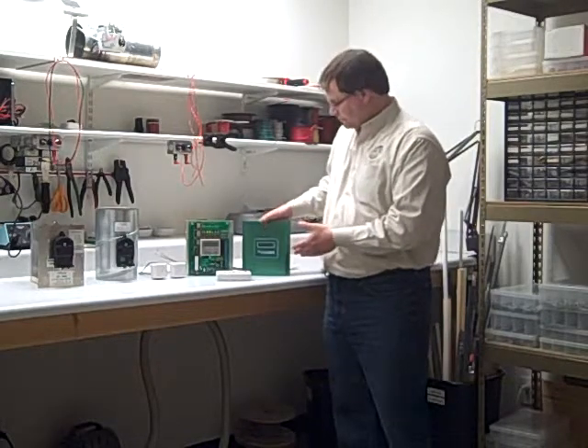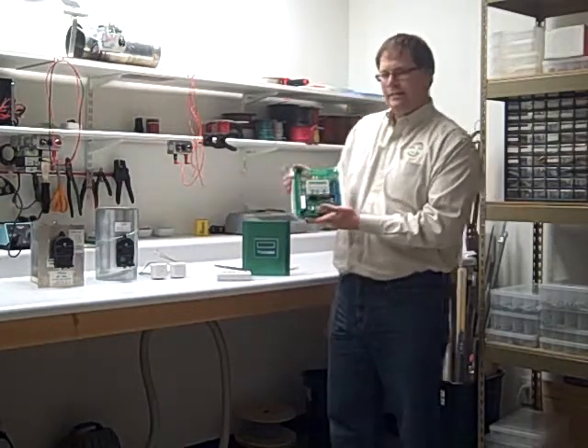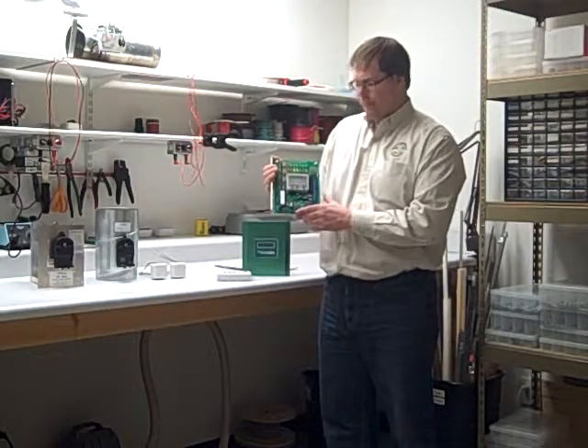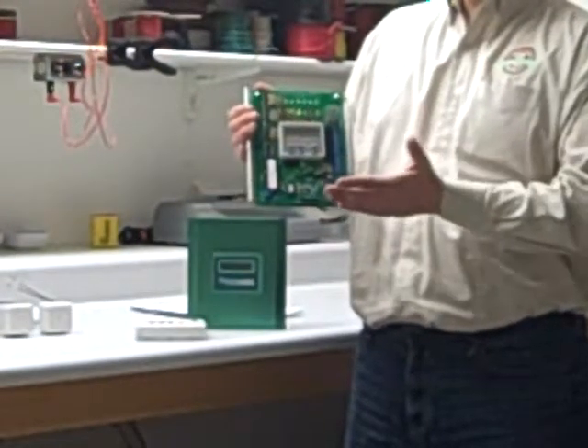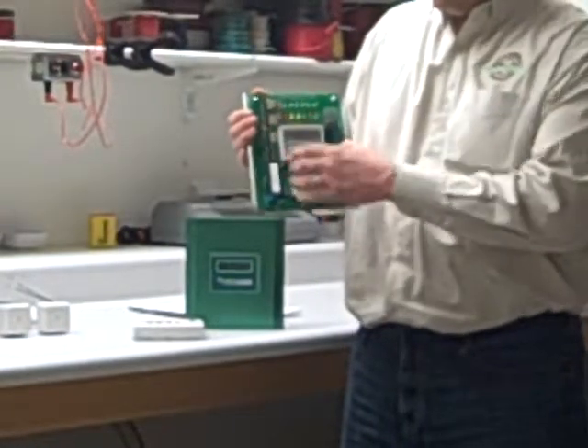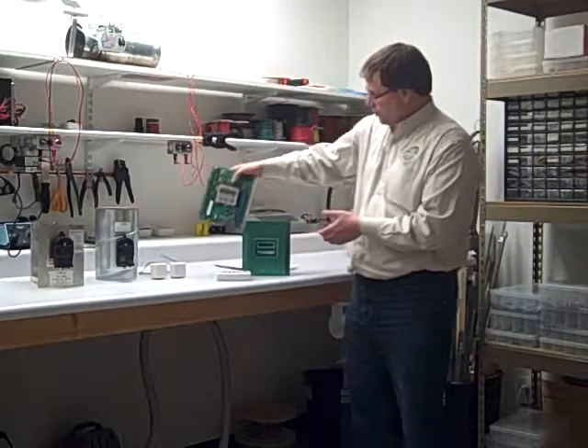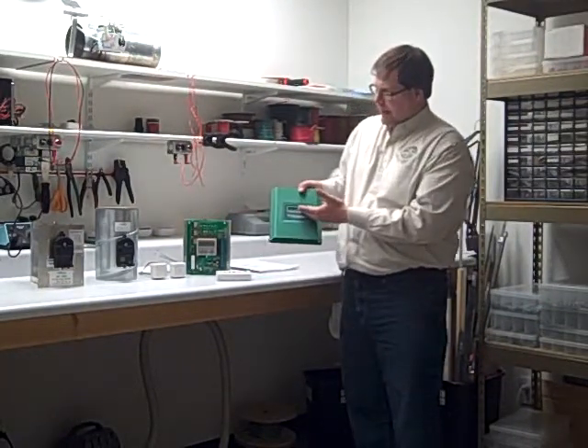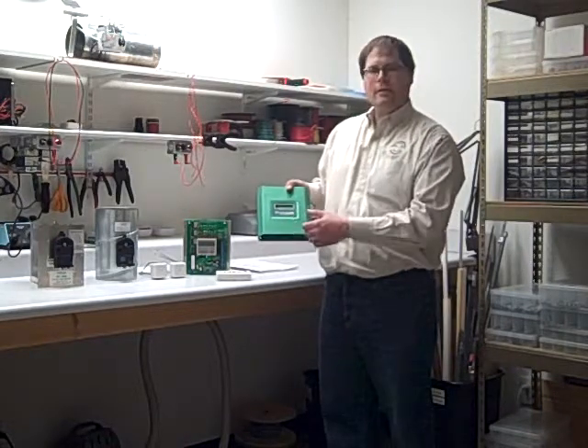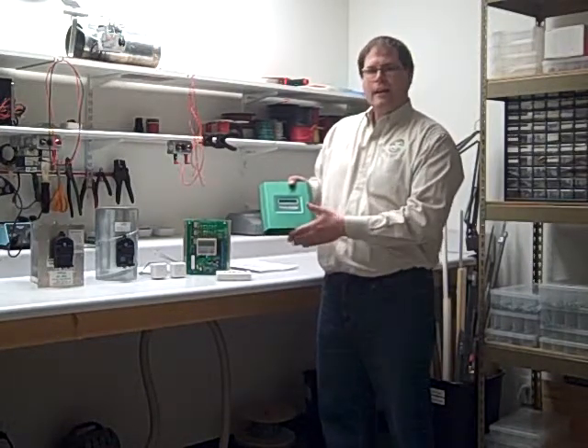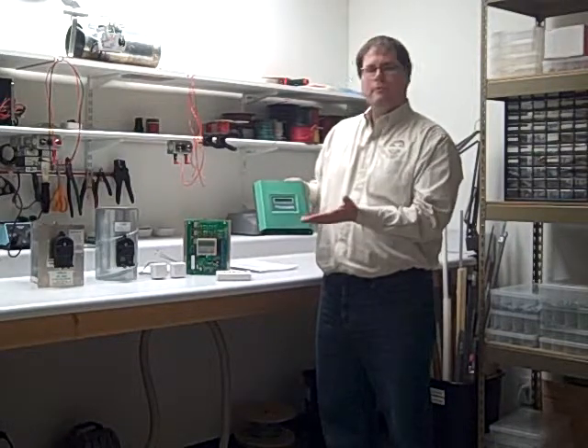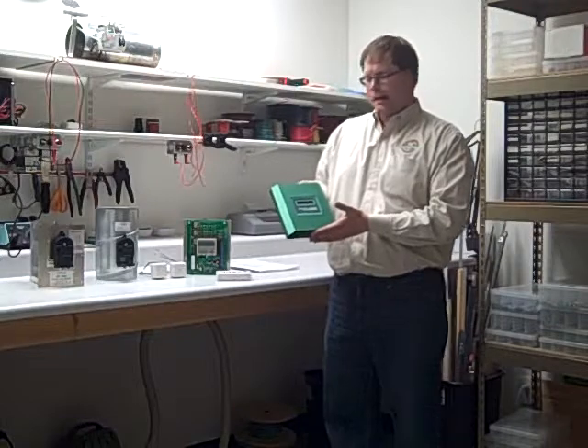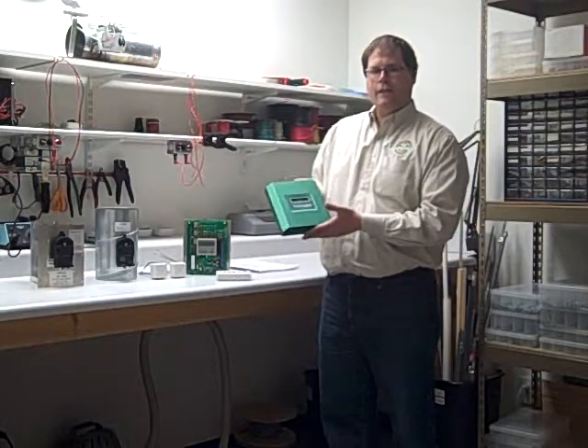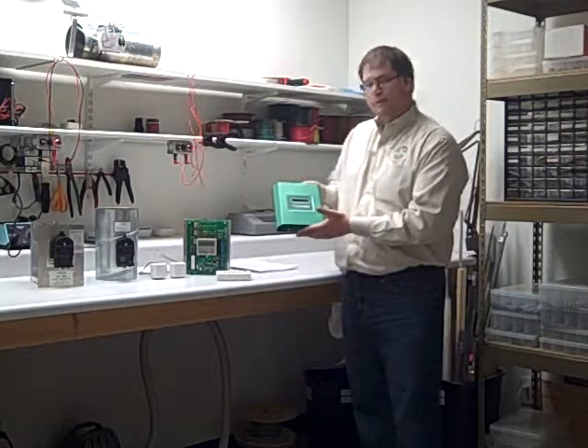You'll also notice in our latest panel, the WCZ-600, we've added what we call the PDM, which stands for Programming Display Module. And this allows you to configure the entire panel as well as see current status and do troubleshooting, all right from a simple interface with a 2-line display. The other really neat thing is that when the cover's on, you'll still be able to see the display. The buttons will be hidden so that the homeowner or building owner doesn't come up and start playing with things. But if there was an issue, they could come up to the display, see what was going on, as well as it'll display your company name and phone number so that they know who to call if there happens to be any issues with the zoning system.